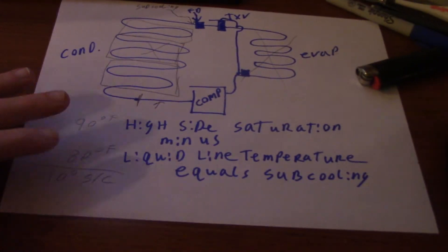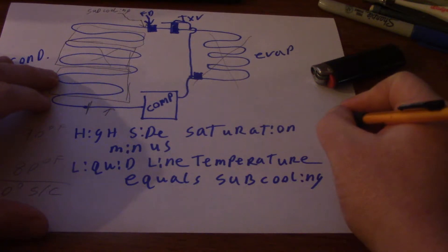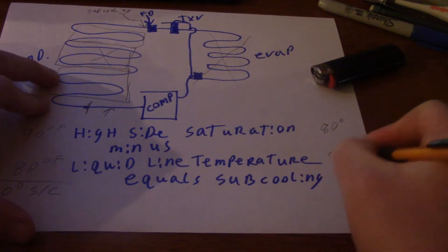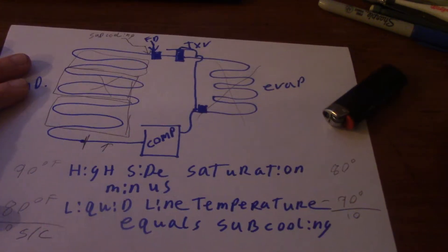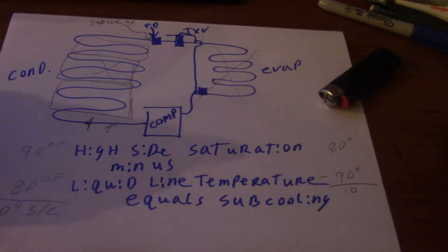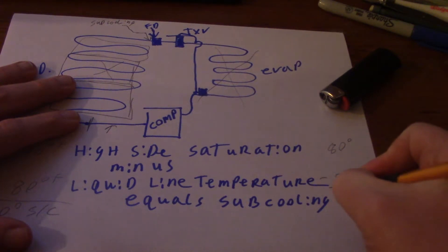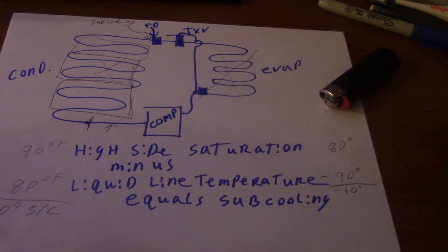If you had a saturation of, we'll say, 80 degrees and a liquid line temperature of 90 degrees, and you did not follow the formula, you might calculate and go, hey, I've got 10 degrees subcooling, this system should be working right. No, you don't have 10 degrees, you did it backwards. You would technically be at negative 10 degrees, which would say there is no subcooling.